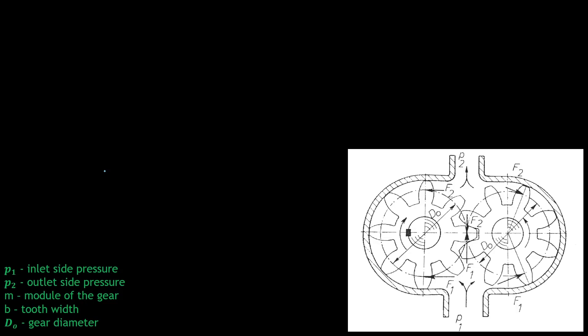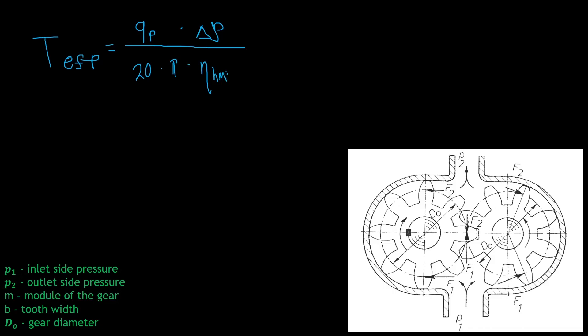If you remember the lesson on efficiency factors from my other course: to get the effective torque for a pump, we relocate the efficiency factor to the denominator. The effective torque for pumps equals the specific flow of the pump times the achieved pressure difference, divided by 20 times pi times the hydromechanical efficiency of the pump. The efficiency factor is in the denominator because we need more torque to overcome losses. If you don't remember, go back and download the lesson on efficiency factors.